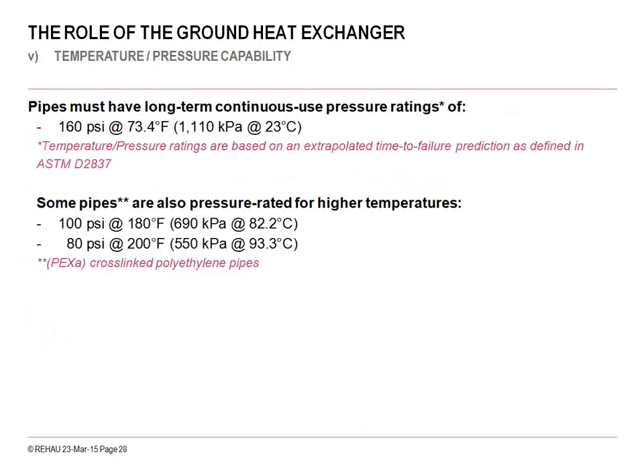Temperature and pressure, you can see some ratings here. To the ASTM D2837 standard, you have a minimum of 160 psi, and generally it's up higher with HDPE and PEXa pipes, in the range of 200 psi. And you can see at the bottom here with some PEXa pipes, some pressure ratings at higher temperatures, 100 psi at 180 degrees and 80 psi at 200 degrees Fahrenheit on PEXa pipes.